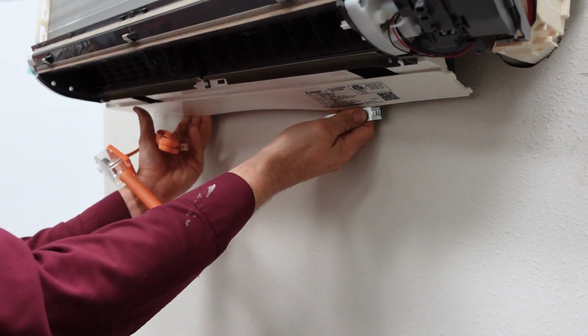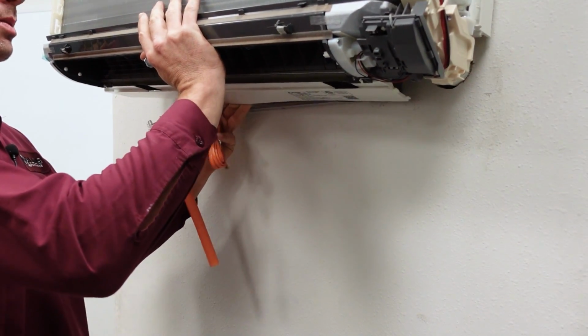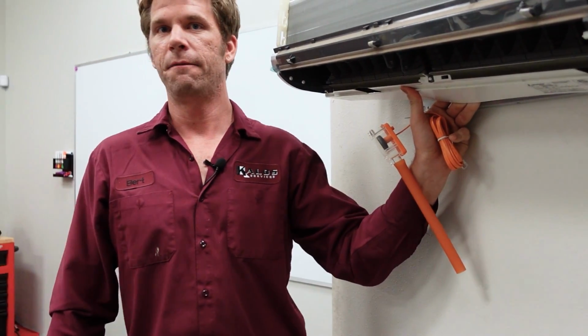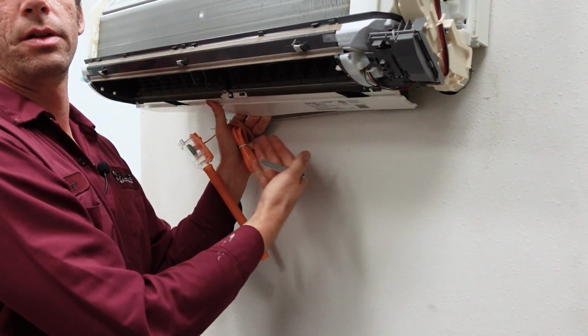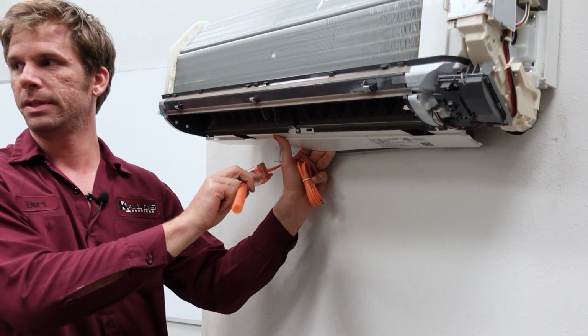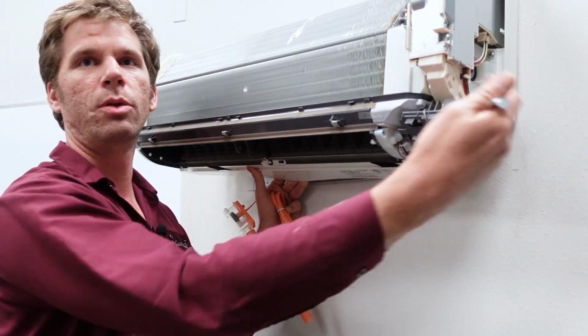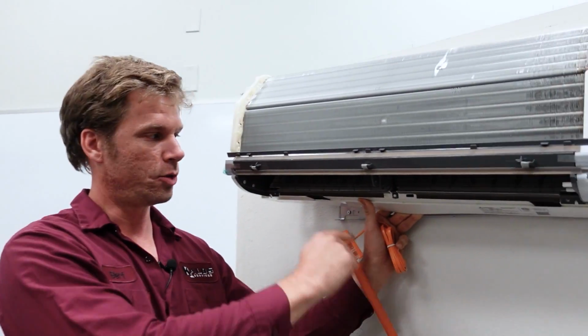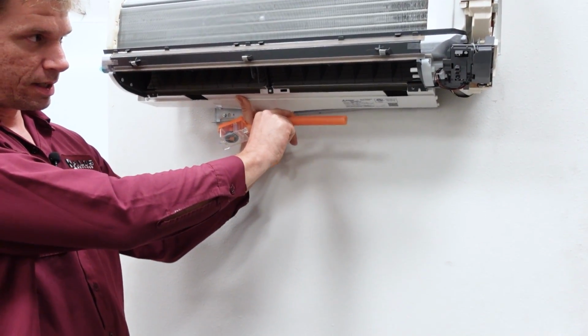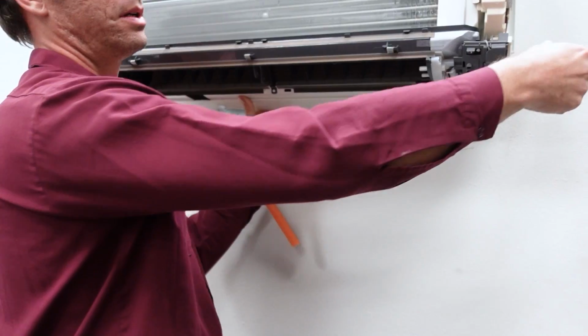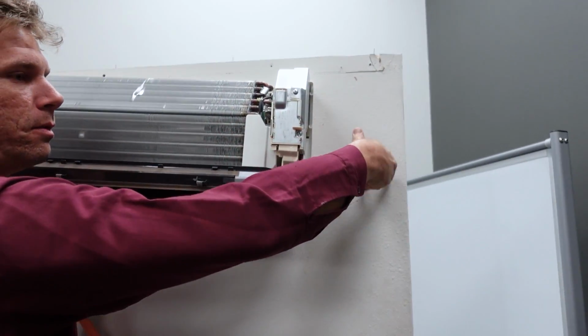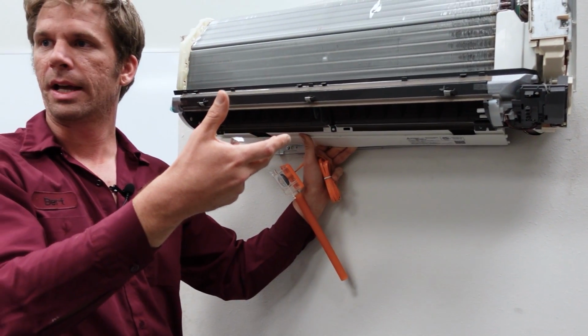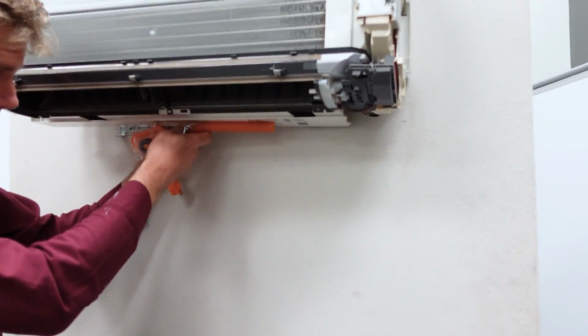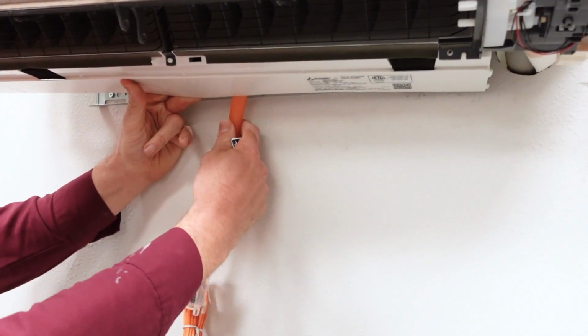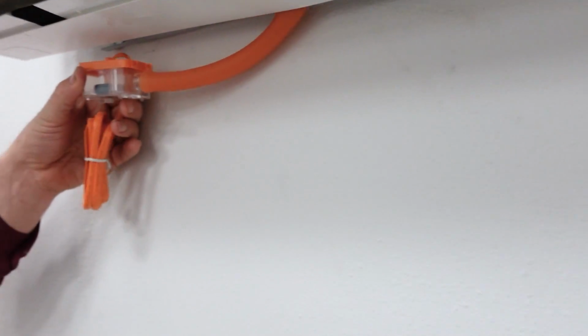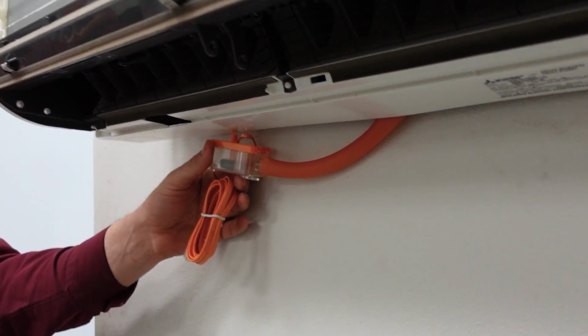Little flat end. So typically, in order to do this, you have to pull the air handler out slightly. Now, if this connection is loose at all, which if the drain runs along sideways, which they often do when they're going into a pump, this is not a pump. The drain's going straight back, and I can't really pull back on the air handler. Whereas with the pump, the drain comes along the back of this and hooks onto this, and you have a little bit more room. Typically, your lines come up here in a line hide that you've opened up, and you can rock the air handler slightly back. And when you do that, then you pull the reservoir down, and you let the air handler just sit like this, and you have access to everything that you need to clean right there.